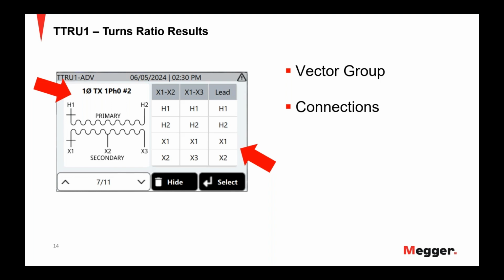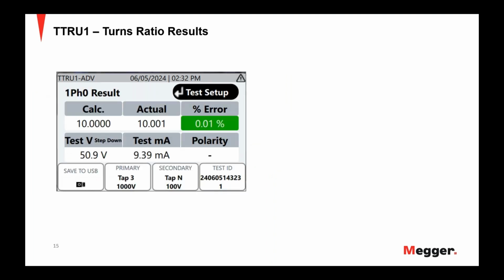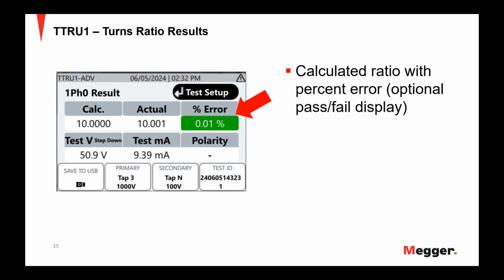tests. And then once you've connected, and if you've entered in some nameplate voltages for the transformer, after completing the test, it will show you the calculated ratio with the percent error. It can also be switched. Instead of showing the exact percent error, you can have it say pass or fail. So if that is how you are typically reporting that in your business or in your utility, you can certainly change the TTRU1 to display the information how you want it. And then very important with these single phase transformers is to note whether it's an additive or subtractive polarity. And we show that right along with the percent error and the excitation current that was drawn during the test.